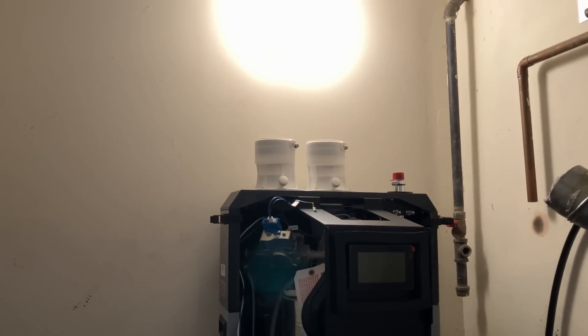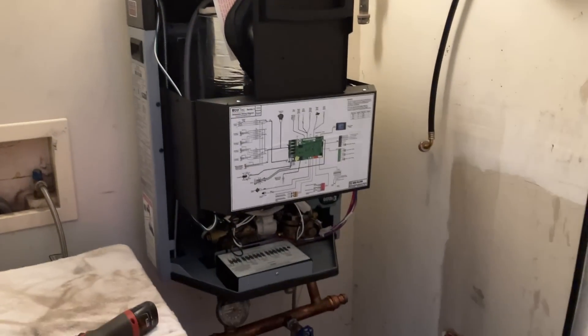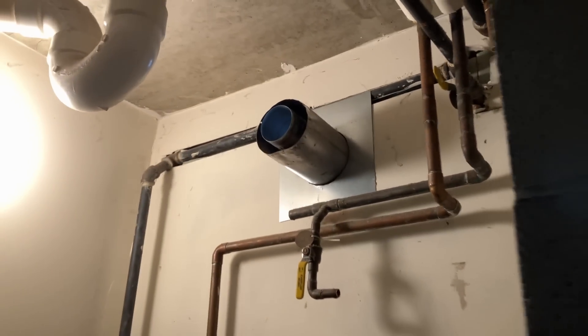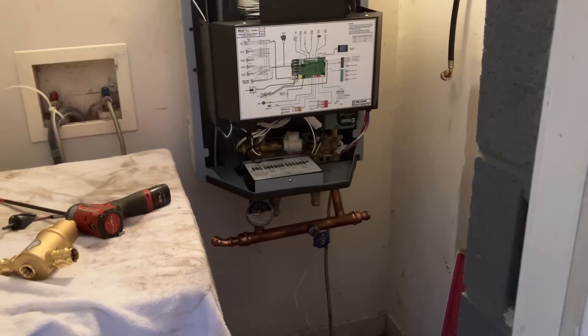We got it on the wall. It's a two-by-four metal-studded wall — literally I could push against the wall and see it move. So I threw in another screw, drilling through the rear cabinet and secured it there as well, and got another one securing to that stud, just so it's a little more secure. There was no plywood in the budget for this — it's actually a budget install, but we're not sparing any expense on materials. We're still doing everything the way we normally do: the spiral vent, Taco ECM circulator, Caleffi pressure-reducing valve. I was able to find a two-inch concentric vent kit in my shop that's been sitting there for years — we're finally going to use that.